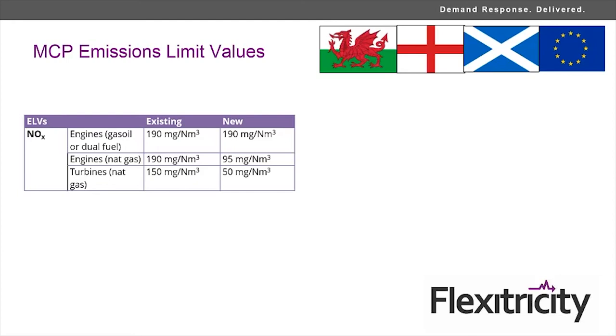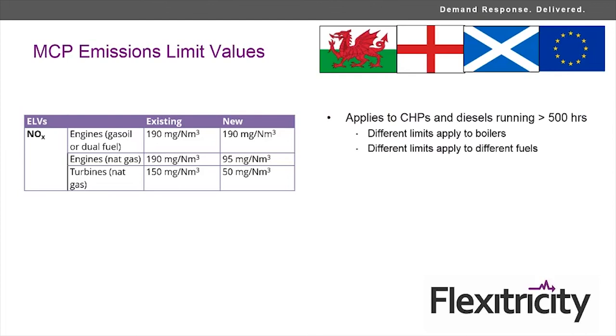There are different emissions limits for things that burn solid fuels or other liquid fuels. The big number to remember is 190 milligrams per normal meter cubed. That's the number that keeps coming up, and I've got to put some context on that. This is MCPs, so it applies to combined heat and power generators and diesels if they run over 500 hours. Generally speaking, CHPs do and diesels don't. The emissions limit values for boilers are different, but they're all there in the legislation.